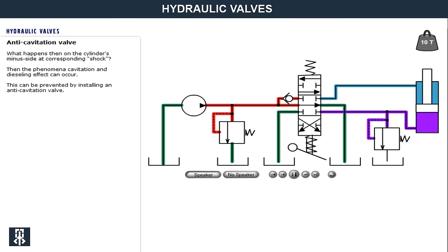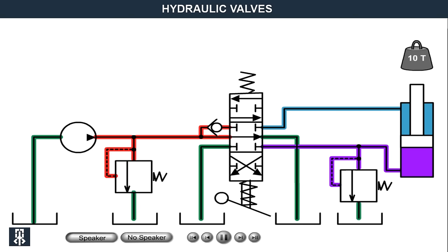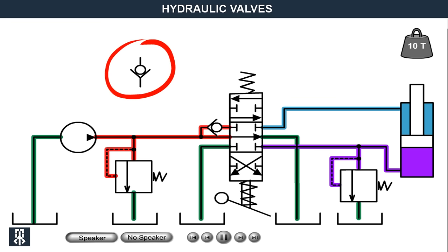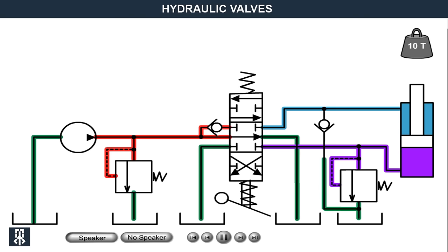When the piston rod moves downward and the volume on the minus side increases, the pressure will drop on that side as the oil volume there is trapped. The phenomena of cavitation and dieseling effect can then occur. Cavitation or dieseling effect can be prevented by installing a non-return valve — called an anti-cavitation valve — between the cylinder's minus side and the tank. When it opens, oil is pressed into the cylinder's minus side if a vacuum is created there.